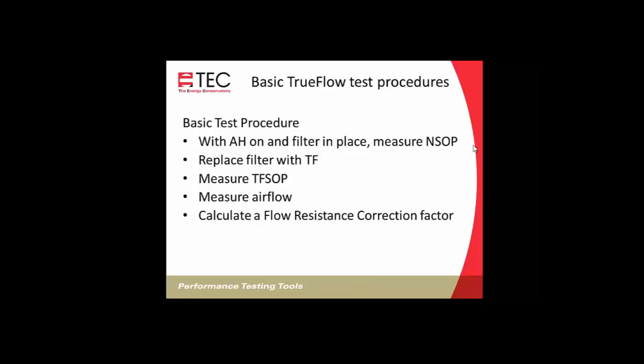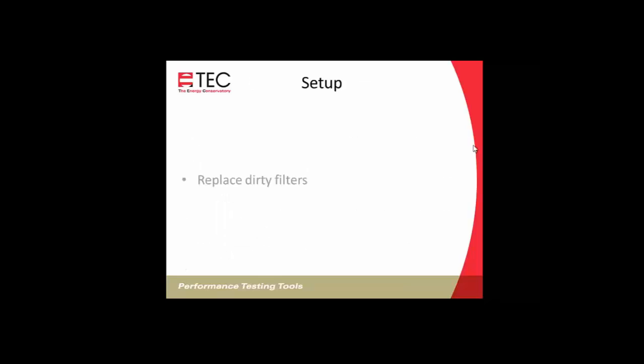We can use either a chart or a formula to come up with that correction factor, and then we'll use that correction factor to calculate the adjusted flow. So our setup, first, if we've got a dirty filter in there, it's a good idea to replace it with a clean one before taking our normal system operating pressure.